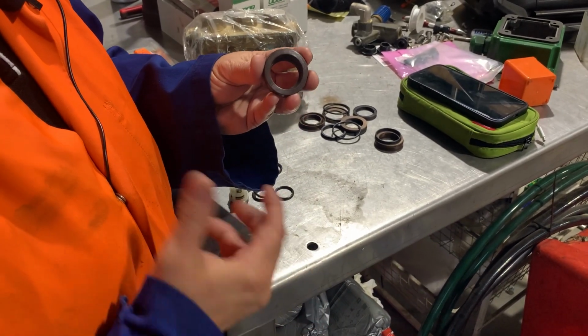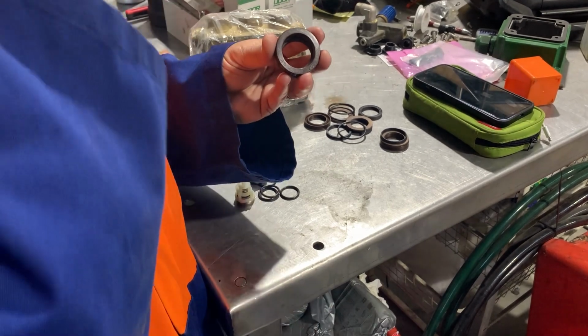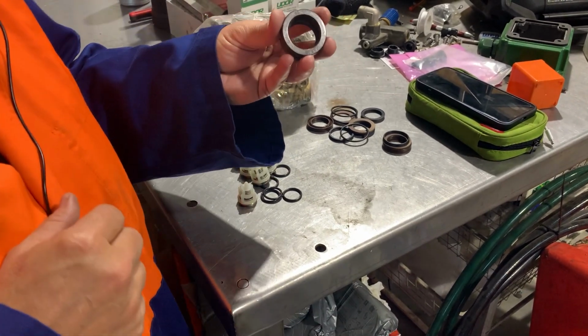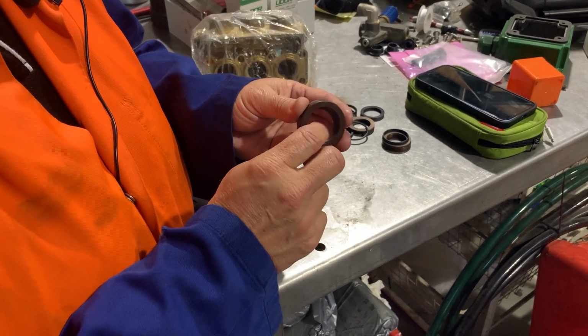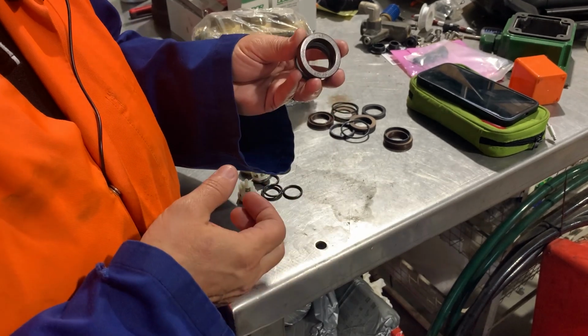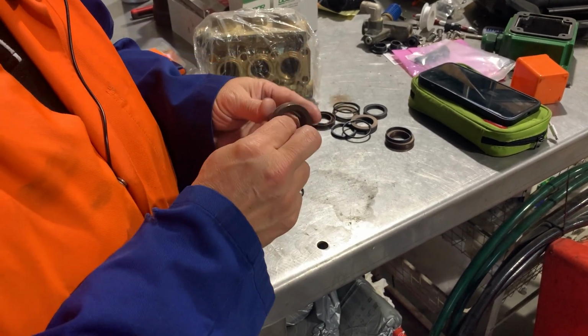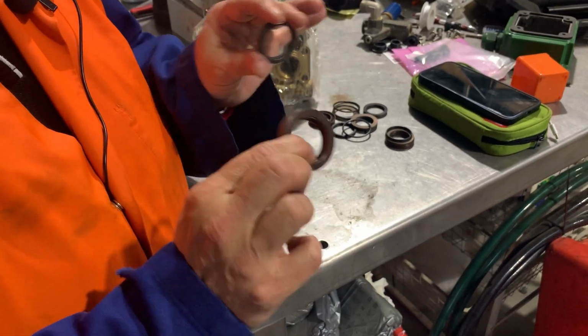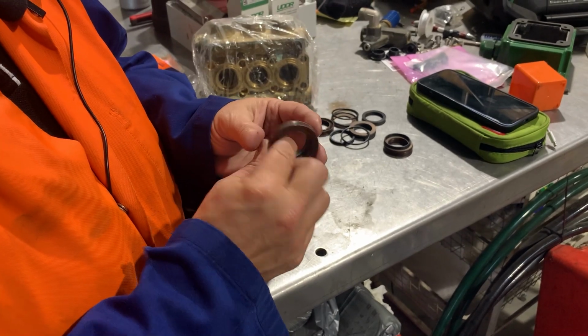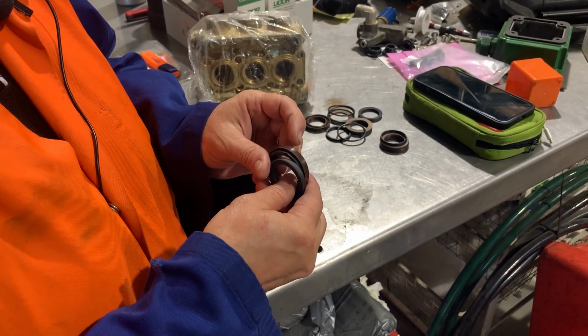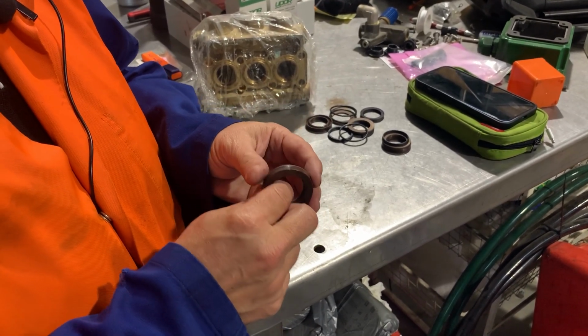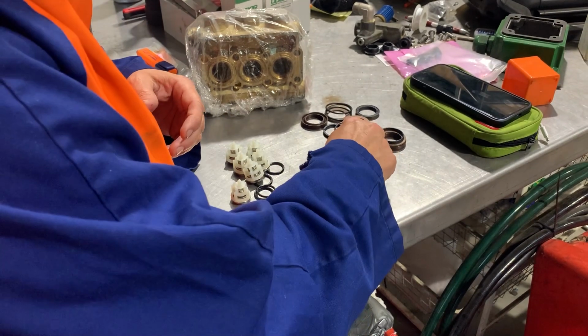Quality of water definitely affects them, so you'll definitely want at least a Y strainer in the system. We've got places where we go down to 1 micron. Depending on your water and how it's set up, the better your water, the longer these will last. It's that simple. I'm not sure of the material, but they're rated for the stainless head that runs in saltwater environments. So that's them.